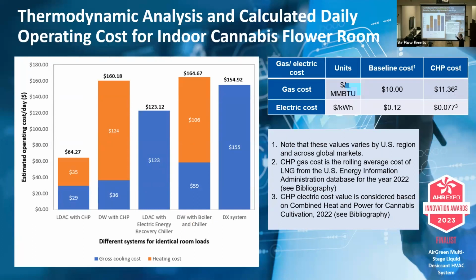This was our study that we presented at the AHR Expo. This is a thermodynamic analysis; we look at the max load of an individual flower room, and we've compared that with a variety of different equipment, using vendor-specific data. We're $64 and change a day at maximum load for a 2,100 square foot flower room with about 575 mature plants, with a weeknight set point of 70 degrees Fahrenheit, 45% relative humidity. So we're $64 a day. What we're compared to, they're 160.